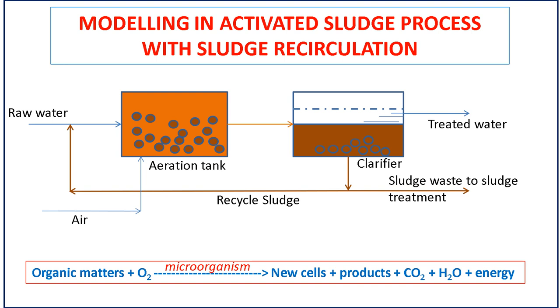During the treatment process, the substrate concentration will decrease until the desired output concentration target is obtained, and the microbial concentration will increase. The liquid mixture from the aeration tank is then put into a sedimentation tank to separate the clear liquid from the processing, with the output substrate concentration and the microbial sludge — called activated sludge.